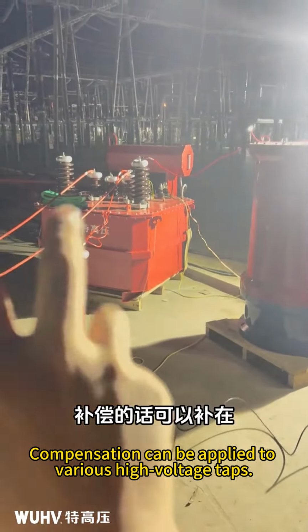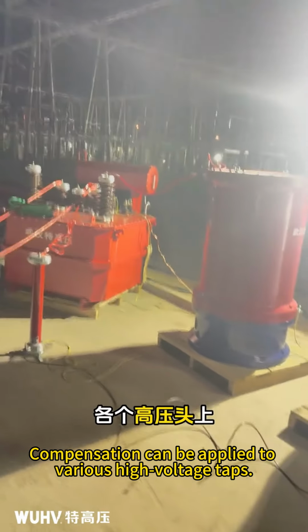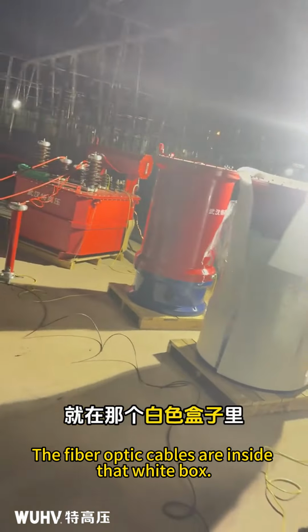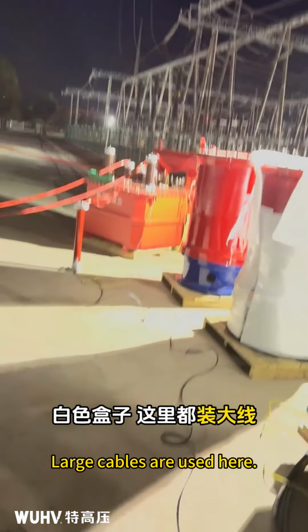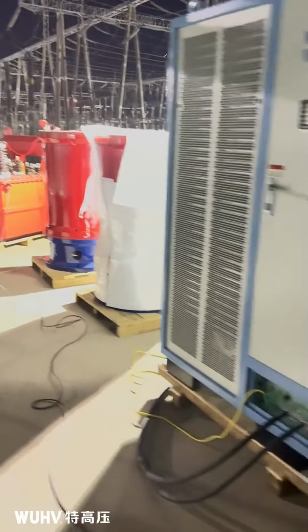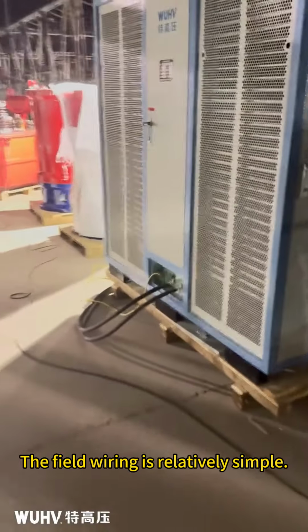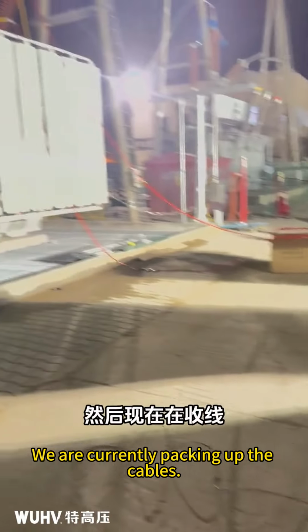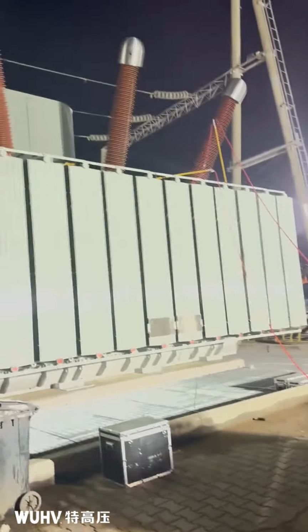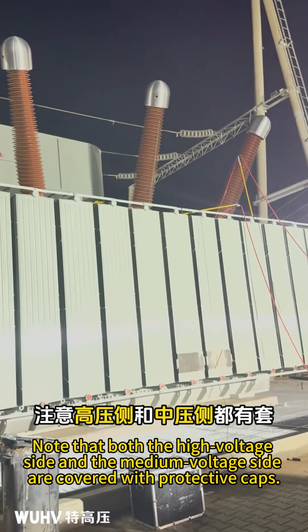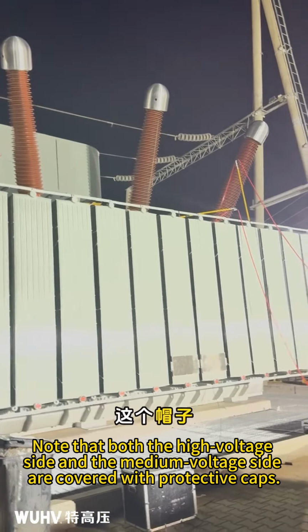Compensation can be applied to various high voltage taps. The fiber optic cables are inside that white box. Large cables are used here. The field wiring is relatively simple. We are currently packing up the cables. Note that both the high voltage side and the medium voltage side are covered with protective caps.